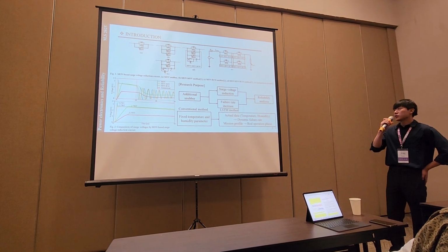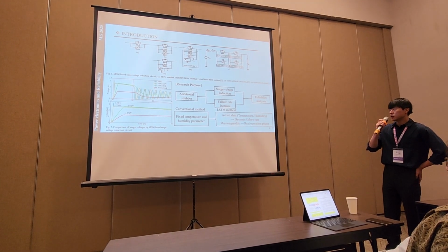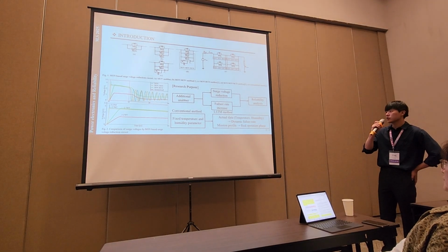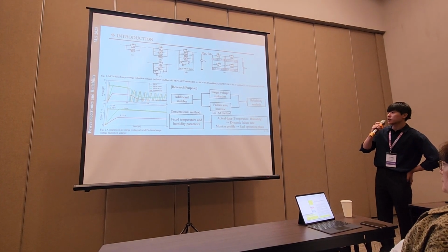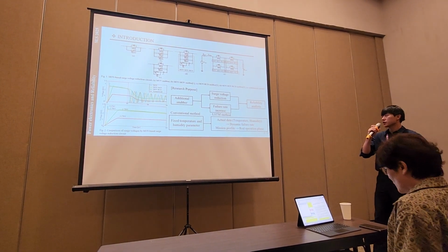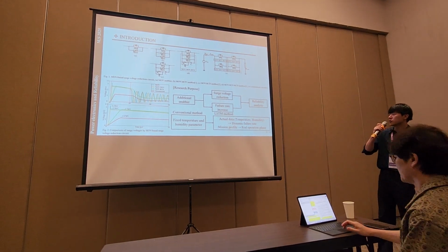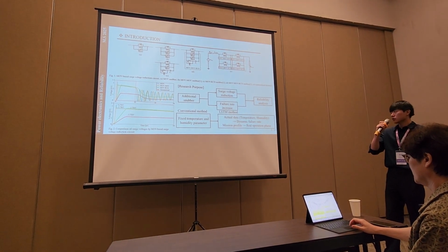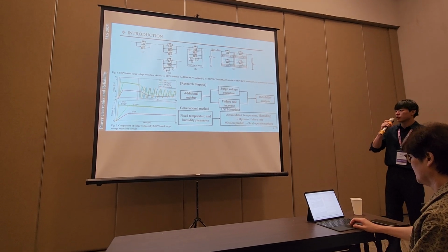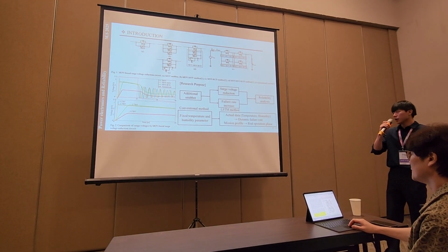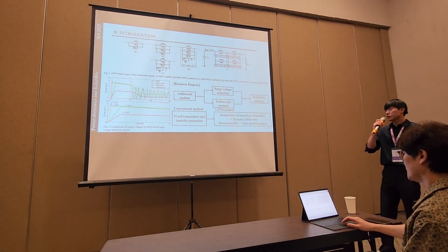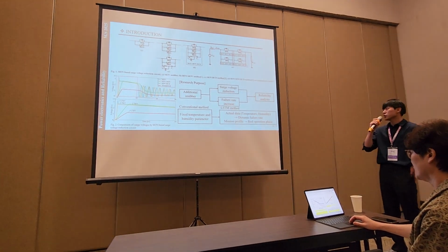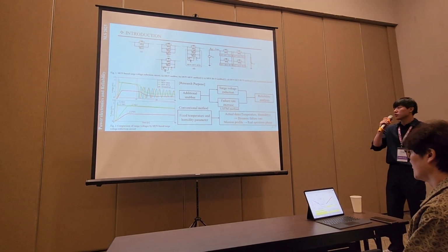First page for the introduction: the DC solid-state circuit breaker has the snubber circuit, as in figure 1A, to reduce surge voltage. The more snubber circuits combine, like figure 1B, C, D, and E, the more the surge voltage reduces, as shown in figure 2. But as the number of components increases, the failure rates also increase. So we need to analyze the reliability of the snubber circuit.